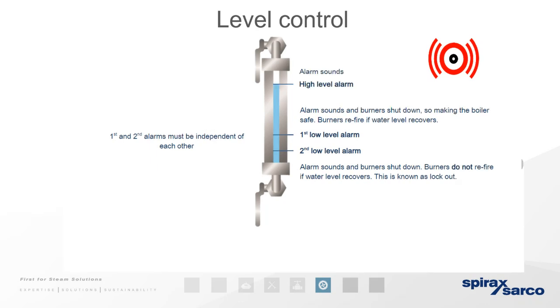Whilst not usually required, many boilers also fit a high level alarm. We were talking about the area for steaming. Many customers also fit a high level alarm in case of a failure where the pump has failed to stop. This means you would eventually get more carryover. The area to produce steam is less, the steam percentage in the boiler is less, so it can be almost as harmful, although it's not a safety issue of the boiler exploding. It becomes harmful downstream, where you've got more carryover, more chemicals, more of everything effectively going down your pipe.